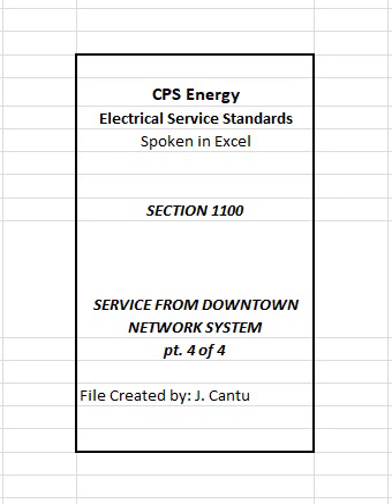B. Location. Customer-owned service disconnecting means shall be located on customer's premises at a point nearest to the customer-built transformer vault or room and CPS Energy fuse pad. 1136 Point of delivery. The point of delivery shall be at the load side of the fuse pad located in customer-built transformer vault or room. Customer shall furnish all necessary connectors or terminals and CPS Energy will make all connections to fuse pad.